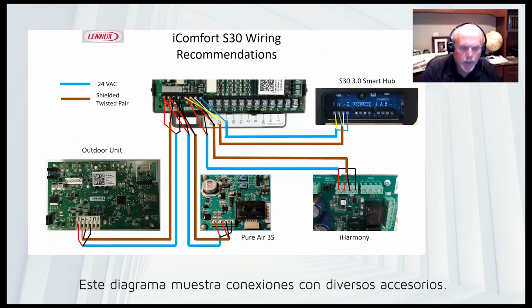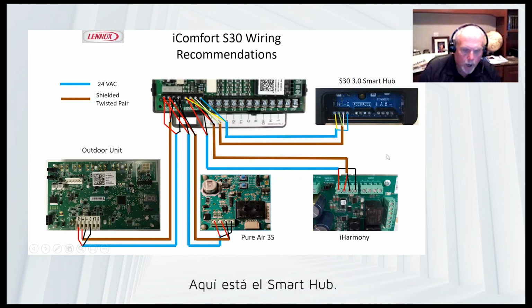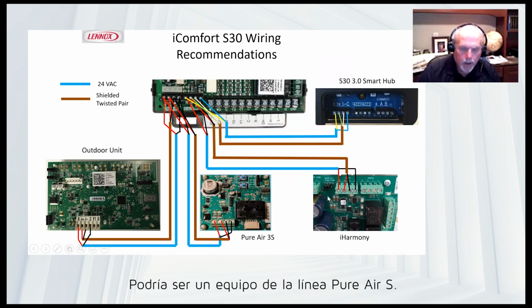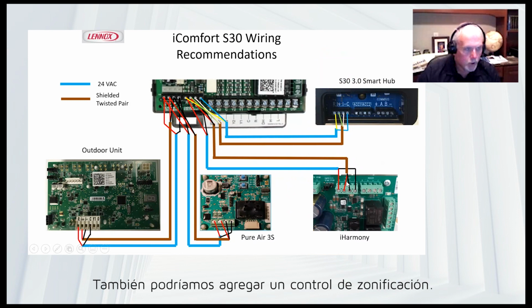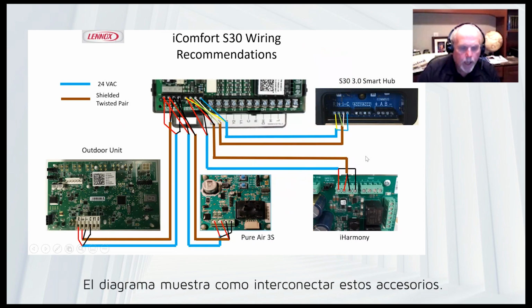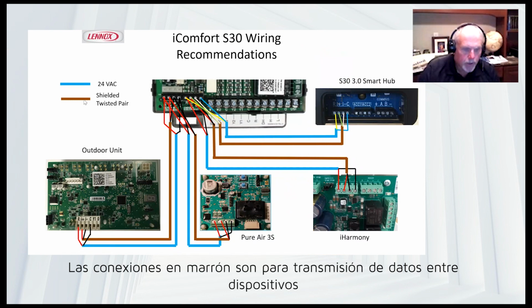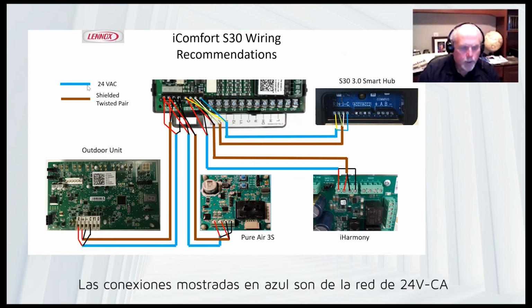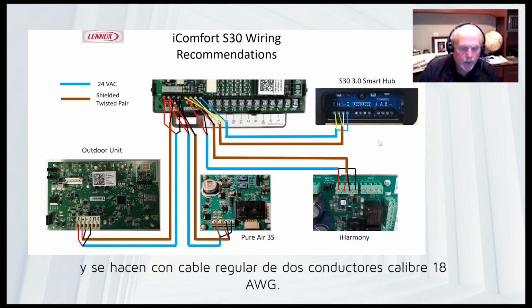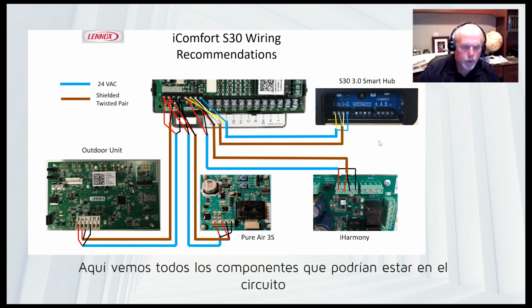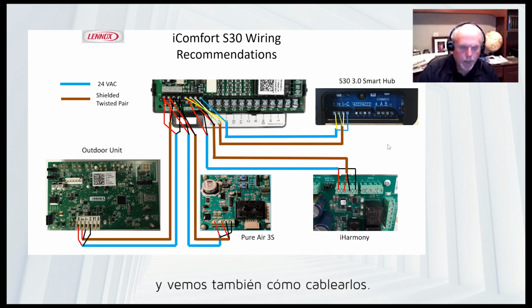Okay, this slide here is a little busy. There are a lot of wires here, but this is with all accessories. Okay, and we have our smart hub. Okay, we have our outdoor unit, which those will be the main ones. You could have a Pure Air 3S. Okay, and we could have a zoning control as well. Okay, so all of these could be in here, and this is showing how to run two conductor cables. One is shielded twisted pair. This would be the brown one, and the regular 24 volt 18 gauge two conductor would be the blue. Okay, so this is kind of just laying out all the components that could be in the circuit and showing how to wire them. Okay, a little busy, but I think you get the idea. This is highly recommended to wire this way.